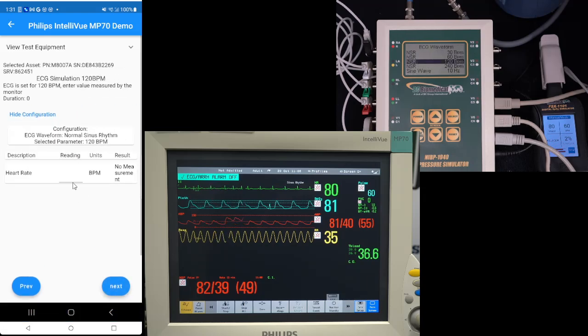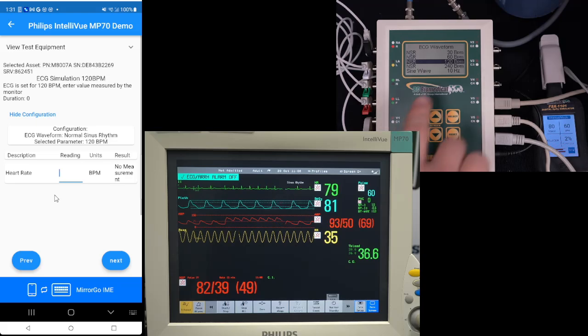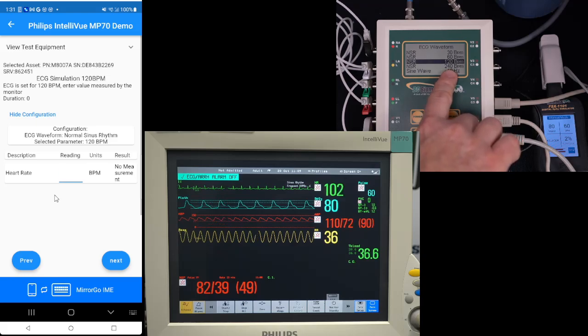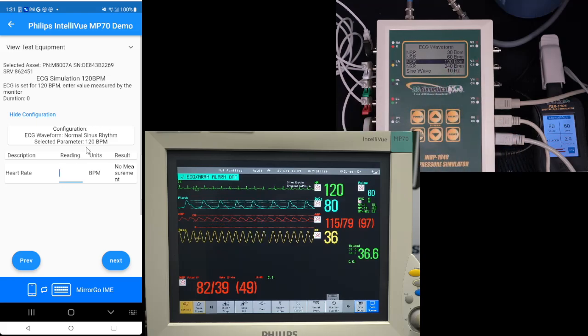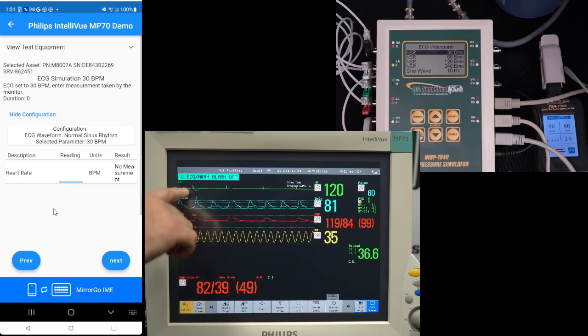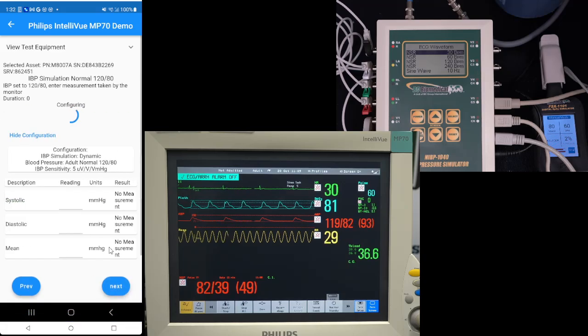Now we can go on and do ECG. We can see the screen here changed to ECG mode. It's selected 120 beats per minute. That's based on this configuration that was done for the test sequence. 120 on the monitor. It's doing great. And then it's going to drop down to 30. So we got 30 beats per minute. And we can see again, now the SpO2 and the ECG are considerably different because I'm not using that sync cable anymore. So we have 30 beats per minute, and that's a pass.